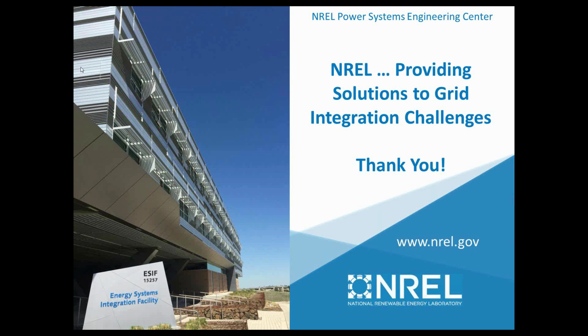But even in the Southeast, we're dealing with this issue. Duke Energy, Dominion Virginia Power, all of these utilities have exactly the same questions and are dealing with them differently. Now, experience with this, like I mentioned, the people that are at the leading edge or bleeding edge of integrating high levels of distributed generation, I would consider HECO to be one of these utilities. They right now are not really worrying about unintentional islanding and are much more focused on allowing all these distributed generation devices to provide voltage and frequency ride-through and support the grid. So it's just something to think about into the future. How do we transition to where we have a lot of this stuff embedded into the system?